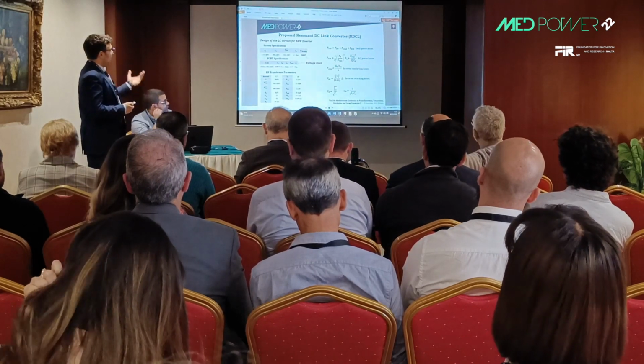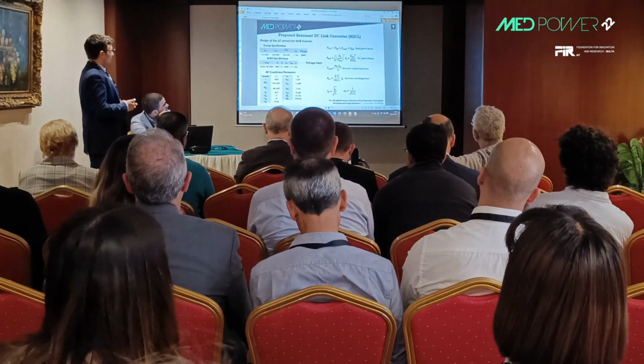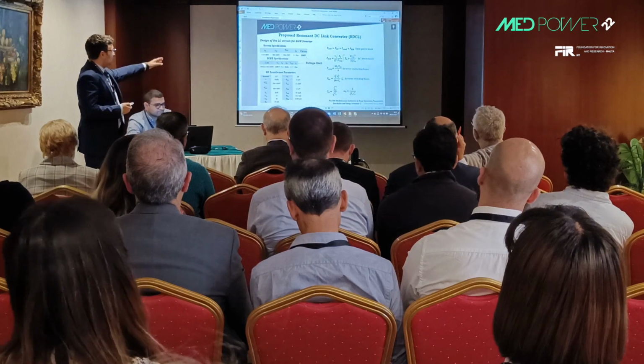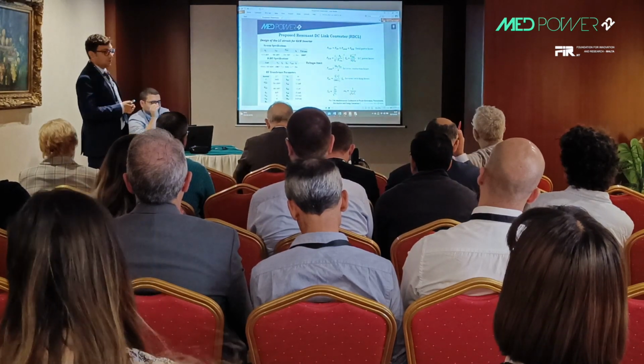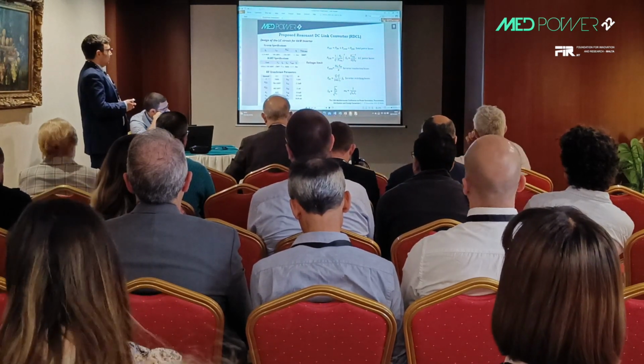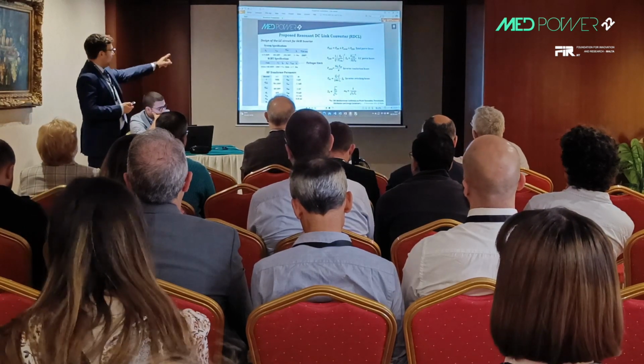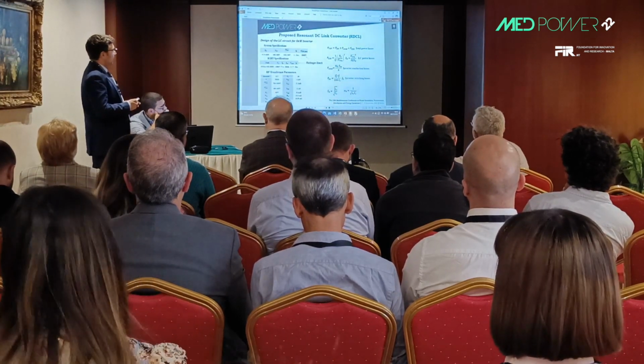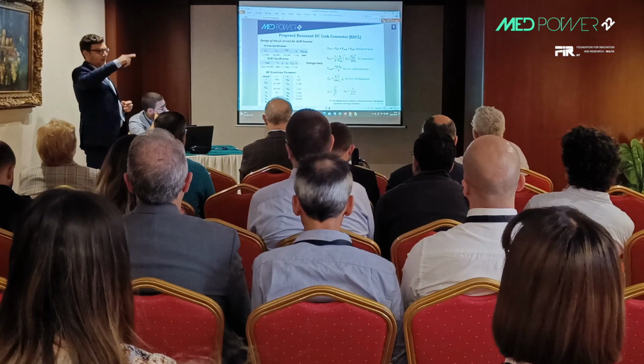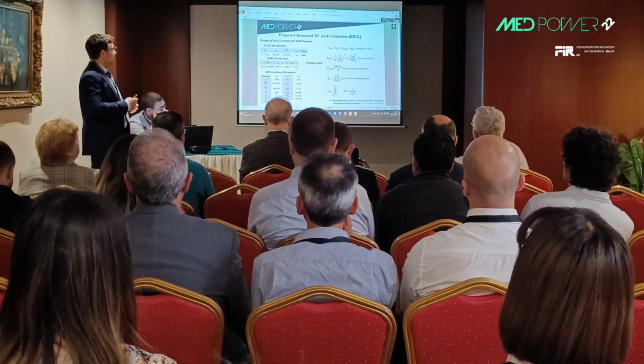We designed a 60 kilowatt inverter using 1200 volt IGBTs, so we must set a voltage limit at 1000 volts. This is the peak voltage of the resonant sinusoidal waveform.